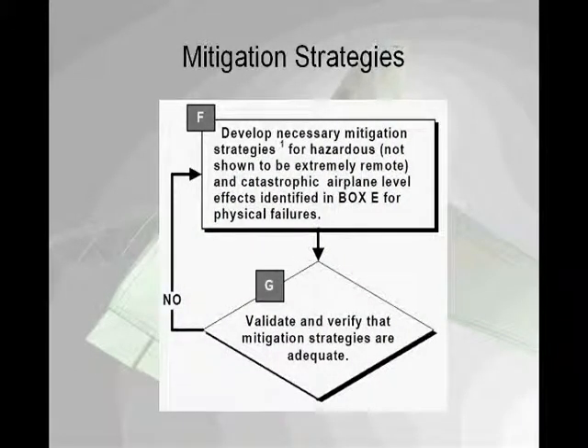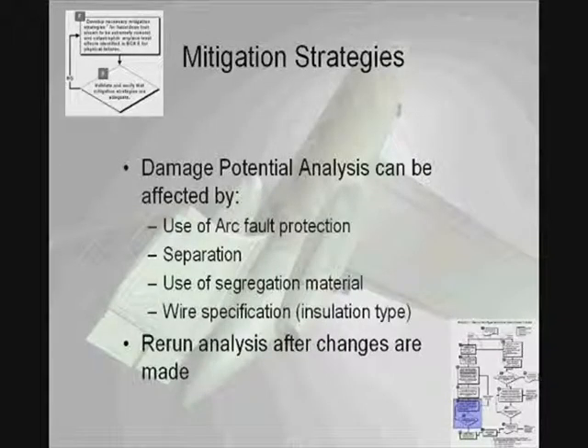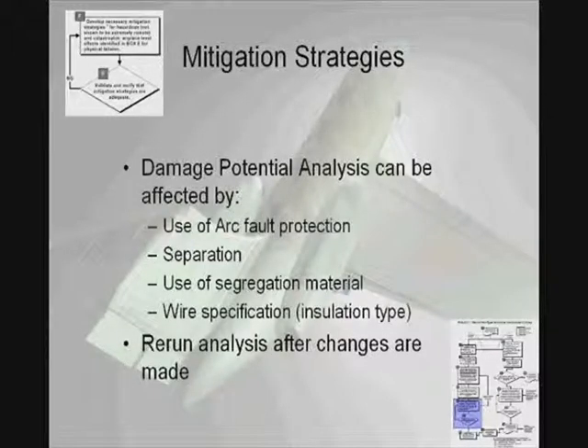The damage potential analysis is affected by a number of parameters, including the use of arc fault protection, separation, the use of segregation materials, and also the type of wire specification, particularly the insulation type.